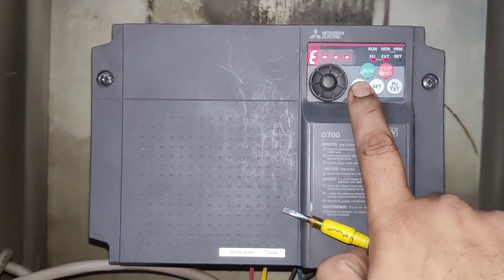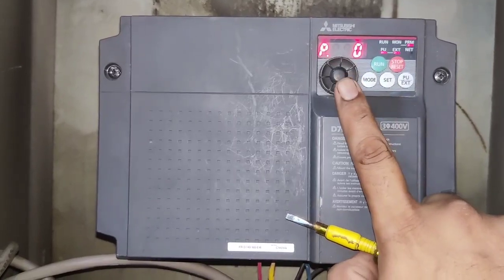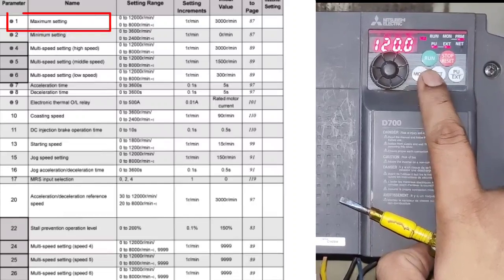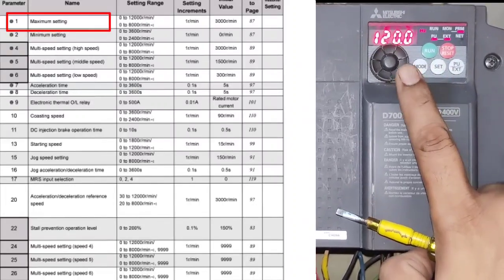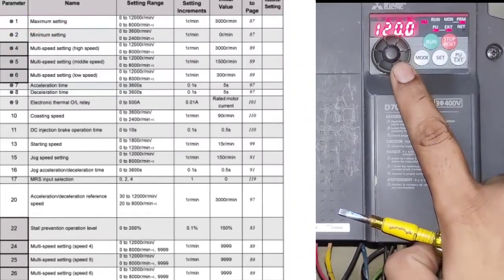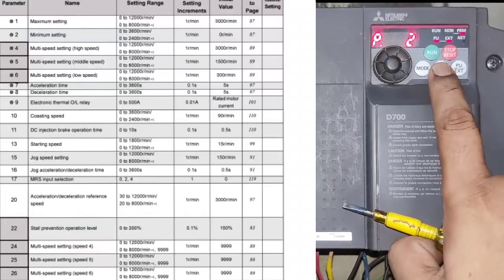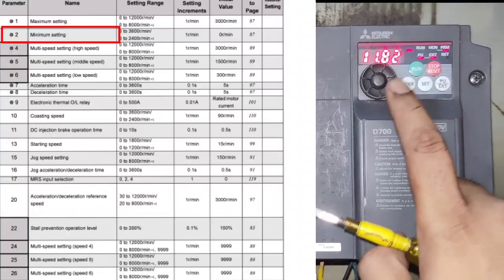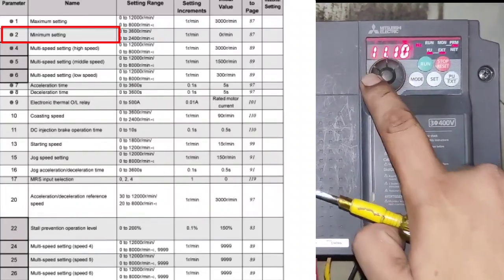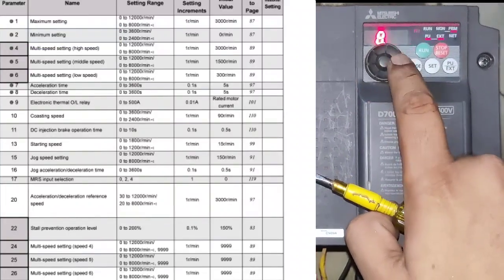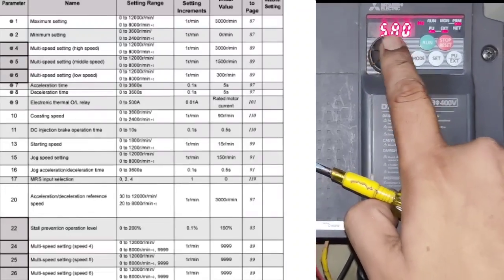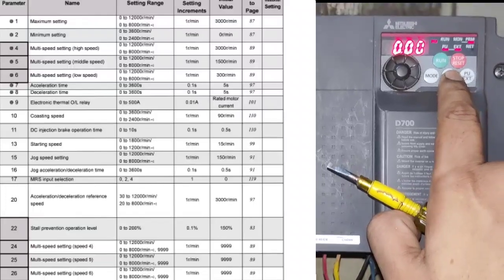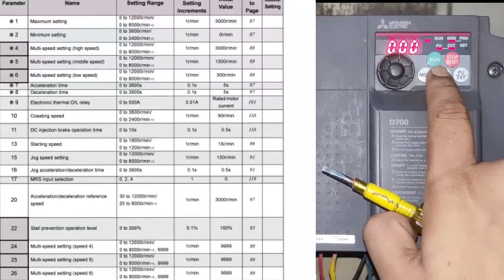Since our motor is small, we set 6 for torque boost. Next, P1 is for maximum frequency — we set 120 Hz. Whatever frequency you want to run your motor at, you can set it in P1. P2 is for minimum frequency, and minimum frequency should be zero, so we set 0 in P2.